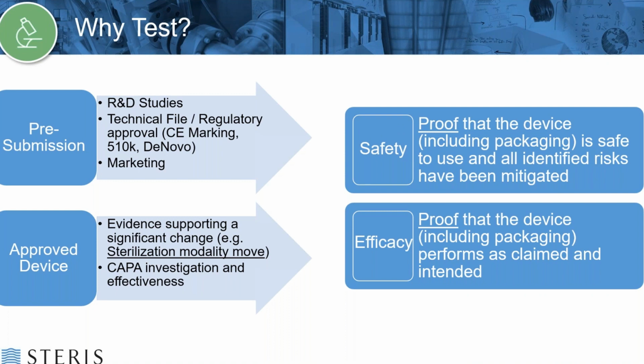So why test? In short, because we're required to, but there's many different reasons why you might need to test. So pre-submission, there's R&D testing that might need to be done during the development of your product. You're going to need to have testing on file for your regulatory submissions, whether it's a 510K or CE mark or any other sort of regulatory approval. And also for marketing, your product's packaging and the product itself are going to have some unique characteristics that you might want to be able to market towards potential customers.